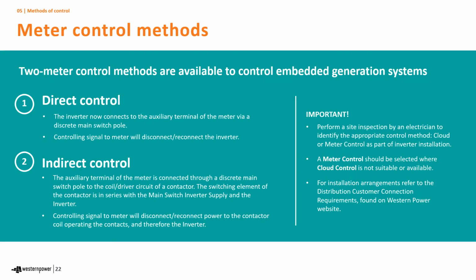With meter control methods, we use two methods to control embedded generation systems. There's what we're terming direct control, and essentially the meter is connected to the inverter system via the auxiliary terminal and the additional pole on the main switch. When we send a controlling signal across our comms network to the meter, the switch will open and will disconnect or reconnect the inverter.